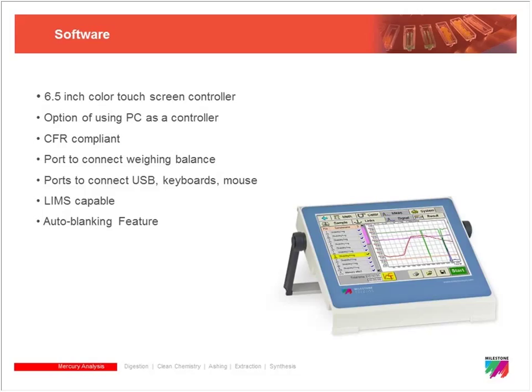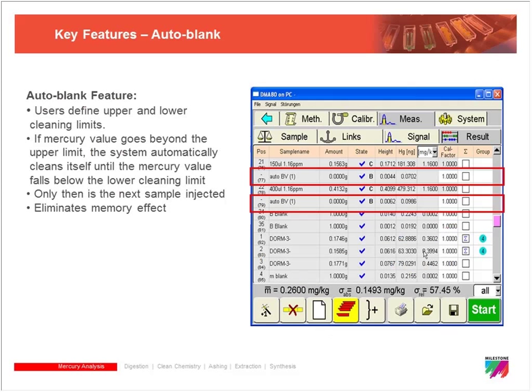One of the key features that the software has is an auto-blanking feature. This allows a user-generated upper and lower limit for how clean the system should be before continuing an analysis. So if you're running a variety of samples, some higher concentration fish samples and some lower concentration plant matter or soils, you can run them all in the same analysis cycle. By defining this upper and lower cleaning limit, your high samples will run through the system as normal, and then the software will automatically run a cleaning cycle so that there's no chance of mercury carryover from your high samples to your low samples.